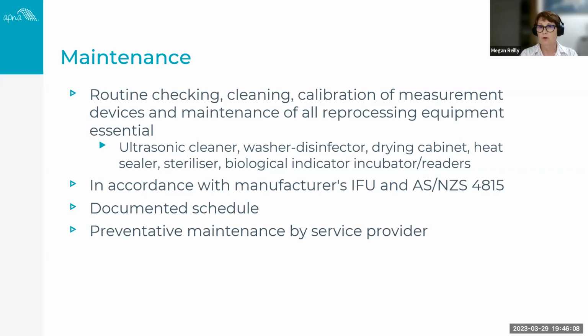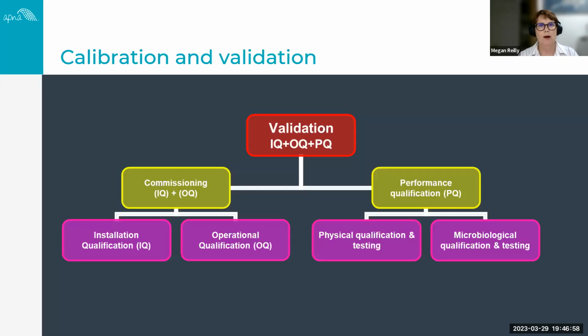So again, you refer firstly to the manufacturer's instructions, what they require, and you also look at 4815. Your preventative maintenance should be undertaken by a qualified service provider that is actually accredited to work on the machine that you have. Ultrasonic cleaners need their daily performance transducer test. They need their annual electrical safety check, as do your washer disinfectors. We need to have documented time and temperature for every cycle. They require a daily test for chemical residue, and again an annual electrical safety check and other maintenance by your service provider. So ensure that all of your equipment is accounted for within your practice.